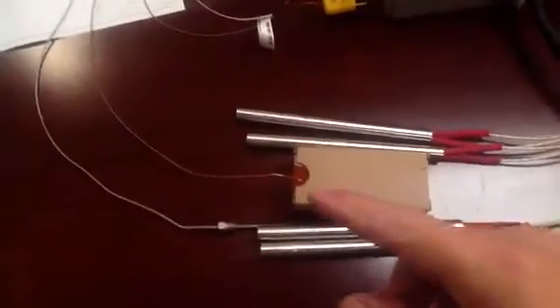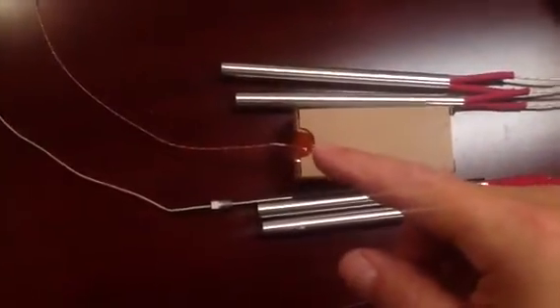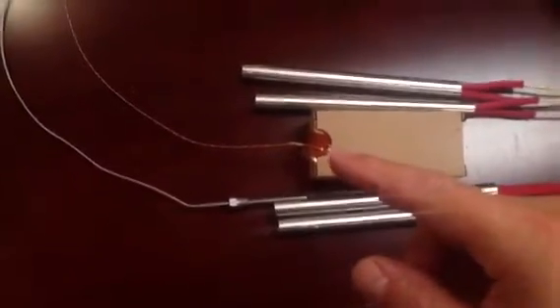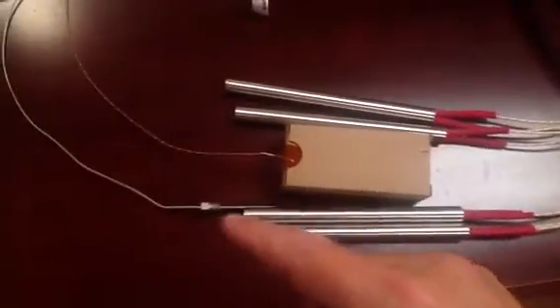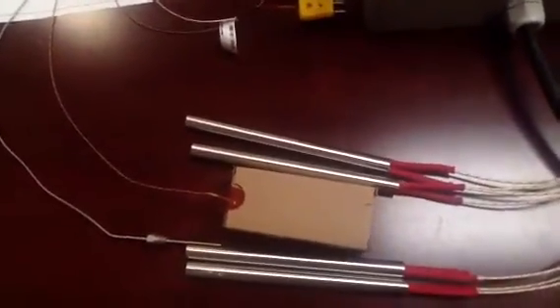So here's our part, and here's our thermocouple, which is a small Kapton peel-and-stick K-type thermocouple. That plugs into one input. The other sensor is monitoring the heaters. These are the actual cartridge heaters that will be in the platen. So we'll be monitoring that heater temperature, and that goes into another input inside the controller. So as this heats up inside the platen, it heats the part, and the part heats the sensor for the part temperature, and we're good.